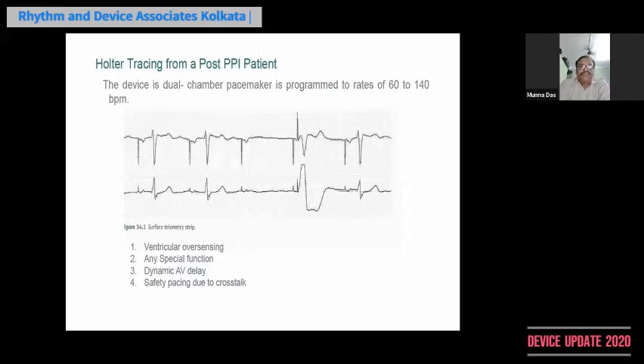It was a special function called MVP, or managed ventricular pacing. It is an algorithm that is put in many of these pacemakers, particularly the Medtronic pacemaker, where it allows intrinsic RV conduction to occur, and it is an AAIR mode that initially operates. Once there are two consecutive non-conducted A waves or P waves, then the device goes into the DDDR mode. Next slide, please.